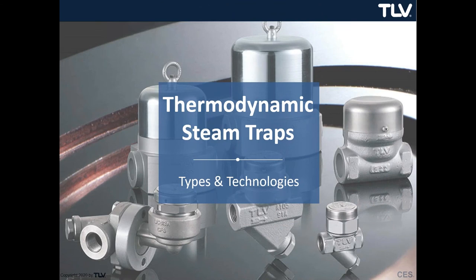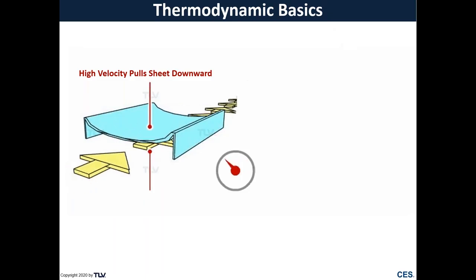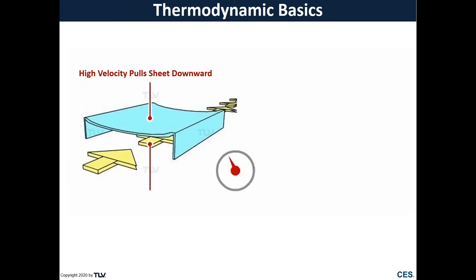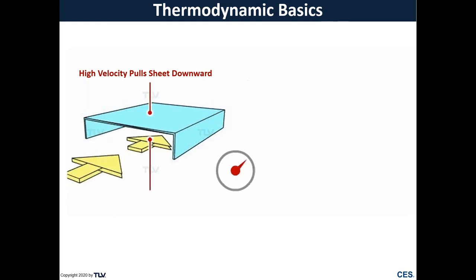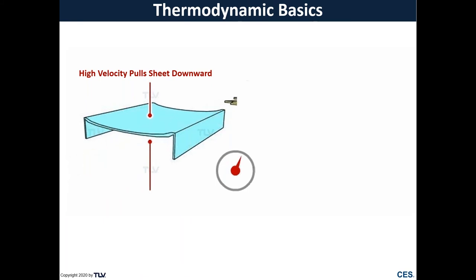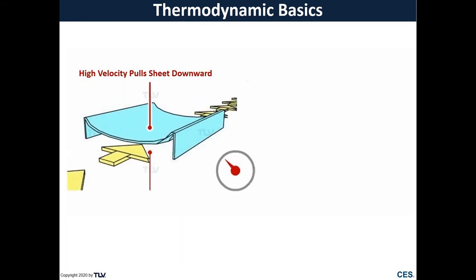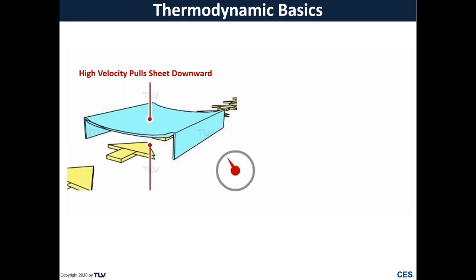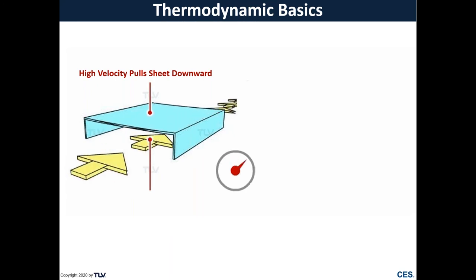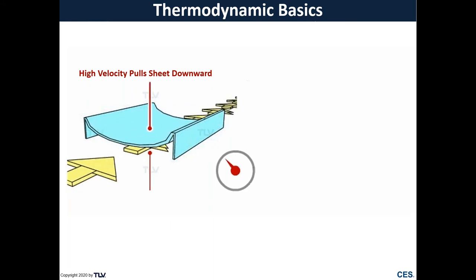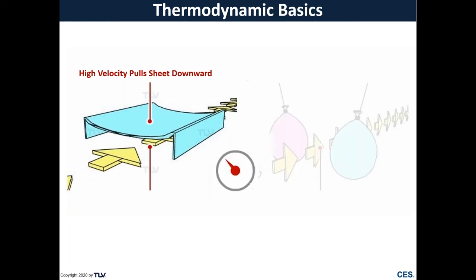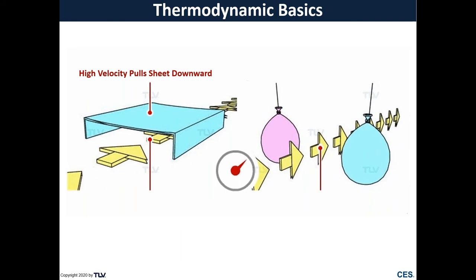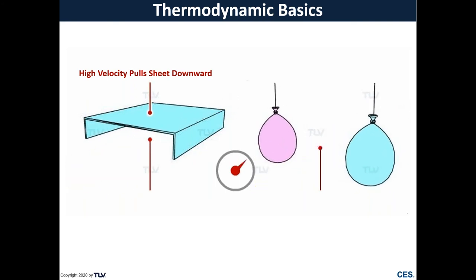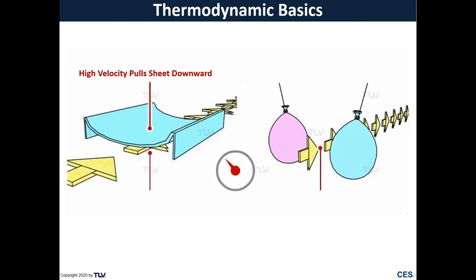The last trap type I'm going to discuss is the thermodynamic or disc trap. Thermodynamic operates based on Bernoulli's principle, so there's a relationship between velocity and pressure. As velocity increases, pressure is going to decrease as well. So you can see here with a high velocity going underneath that sheet of paper, it's going to create a low pressure pulling that sheet of paper down. Another situation, if you had a high velocity going between two balloons, it's going to pull those balloons together because of that low pressure.